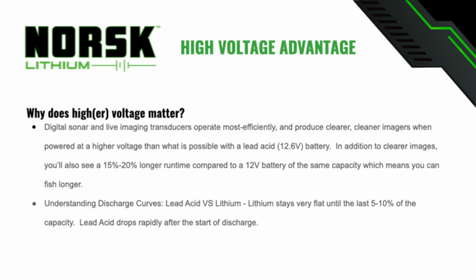Lithium starts at a much higher voltage, and the discharge curve is essentially flat until you get to that last 5-10%, 13.3, 13.4, 13.5, 13.6. It does not drop off a cliff like lead acid does. I've done lots of experiments: new Group 27 battery, you put a 5 amp draw on it, within about 30 minutes you're below 12 volts. So you're already within 2 volts of shut off for these units.